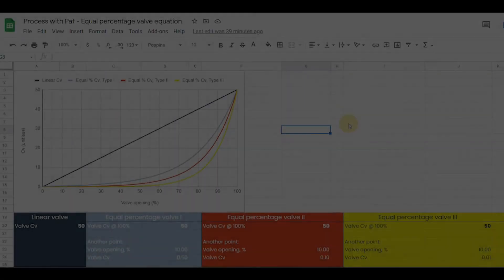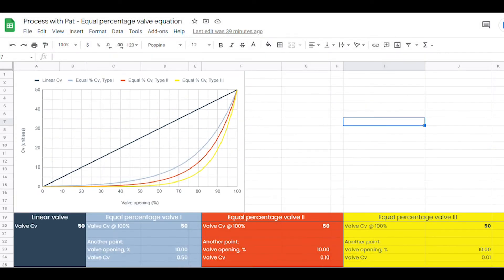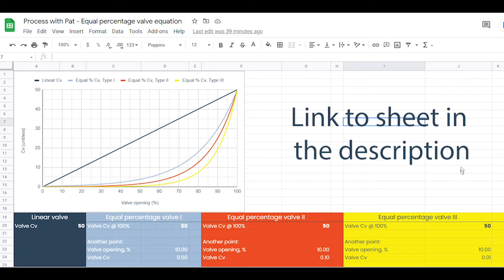The implication of this is that whereas there is only one possible linear characteristic valve with a CV of 50, there are theoretically infinite amounts of equal percentage valves with the CV of 50 depending on how I define these parameters.